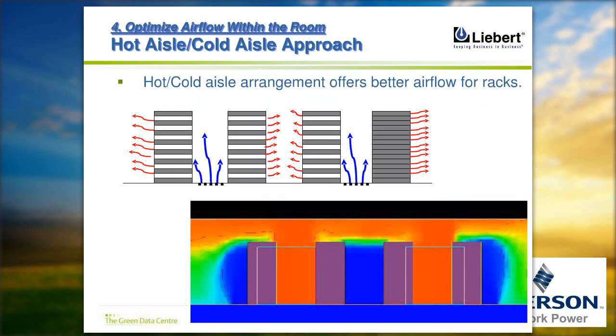Many a customer I have seen open the tile, open the floor grill in the hot aisle, thinking that it's very hot. But in case of such things happening, it is expected that the cold and hot aisle have to be separated. The hot aisle can go as high as almost 30 degrees plus, and the cold aisle can be maintained at least at 22 degrees plus minus 1 degree. So please do not open any floor grills in the hot aisle.